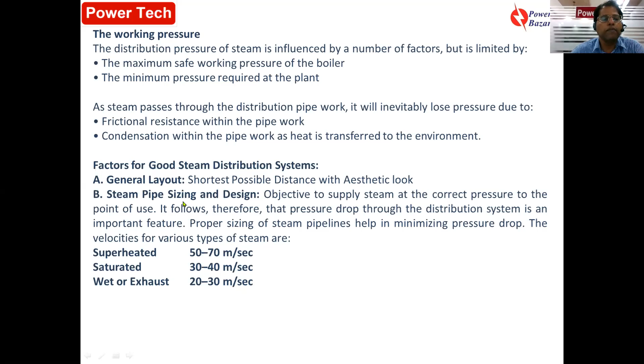The objective is to supply steam at the correct pressure to the point of use. It follows therefore that pressure drop through the distribution system is an important feature. The velocity for various types of steam: for superheated, the velocity should be in the range of 50 to 70 meter per second, saturated 30 to 40 meter per second, and wet 20 to 30 meter per second. So this is the velocity at which the steam should flow. Based on this velocity and volume flow, the steam pipe has to be designed accordingly.